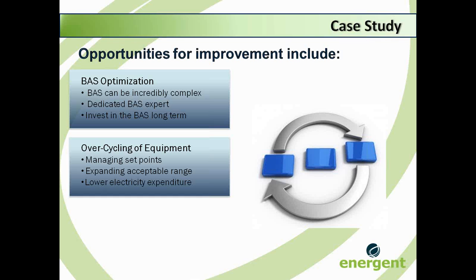With the improvements in HVAC systems, there is an increase in the expectation of facilities teams to manage the set points of the hospital much more closely. Because the system can manage a hospital within 1 degree Celsius, 24 hours a day, does it really mean it has to? When there's a narrow band of managing set points, equipment tends to be cycled on and off frequently. This can cause an increase in energy expenditure as equipment ramps up to temperature, and often these large pieces of equipment are not built to cycle on and off all the time. It can reduce the life expectancy of large capital upgrades.